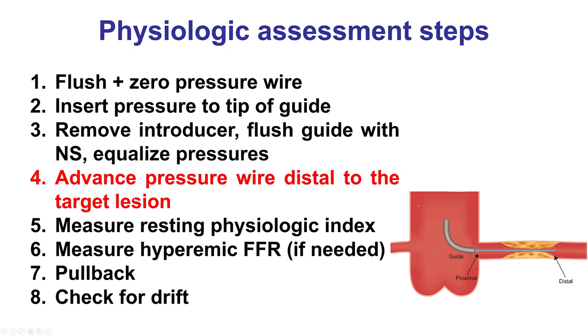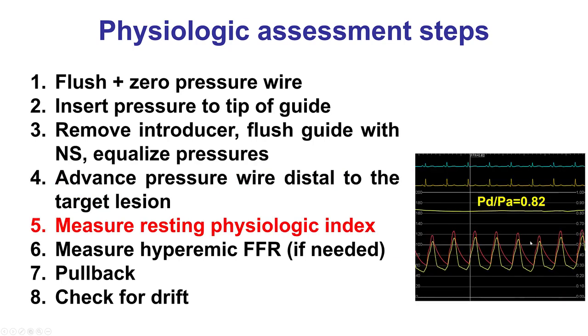Step four is to advance the pressure wire distal to the target lesion. This can sometimes be challenging because pressure wires are not quite as torqueable as standard wires, but in the vast majority of cases they can be delivered. Step five is to measure a resting physiologic index depending on the system being used.